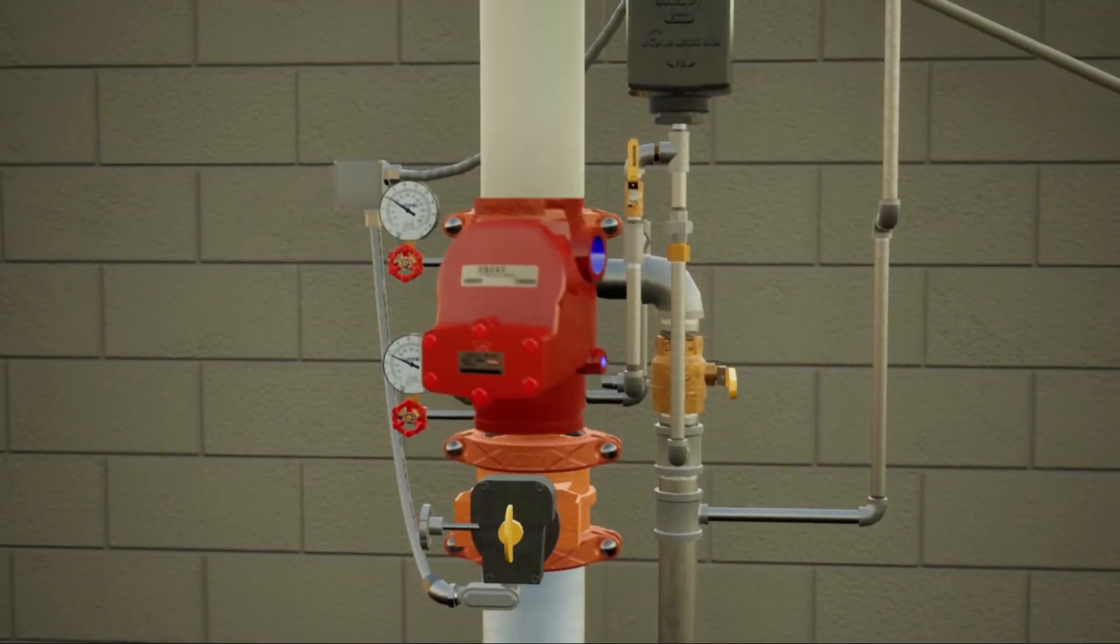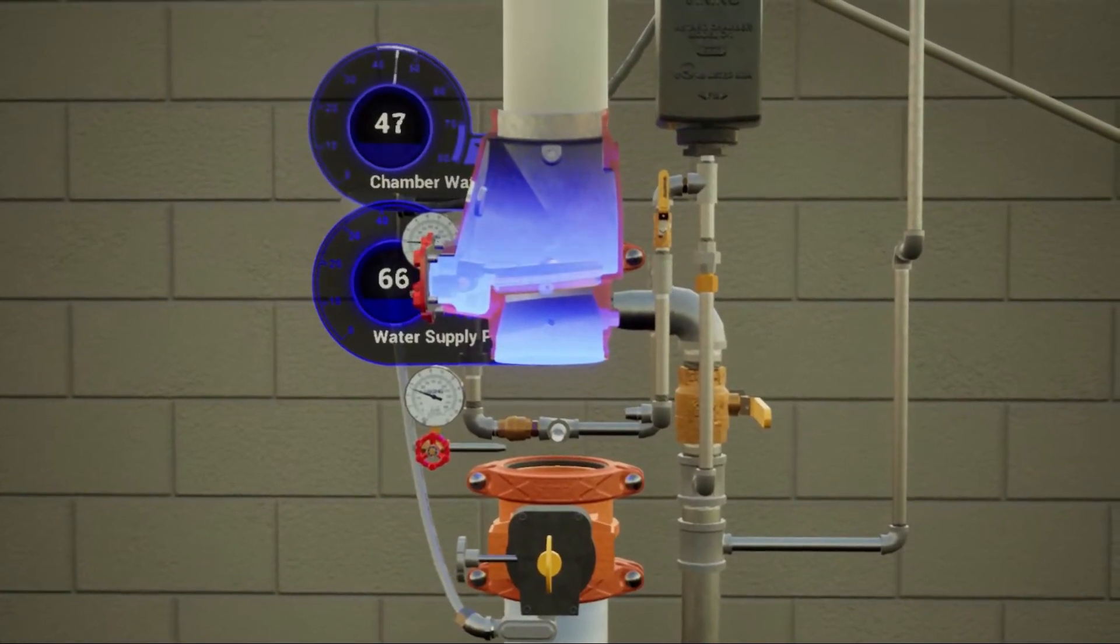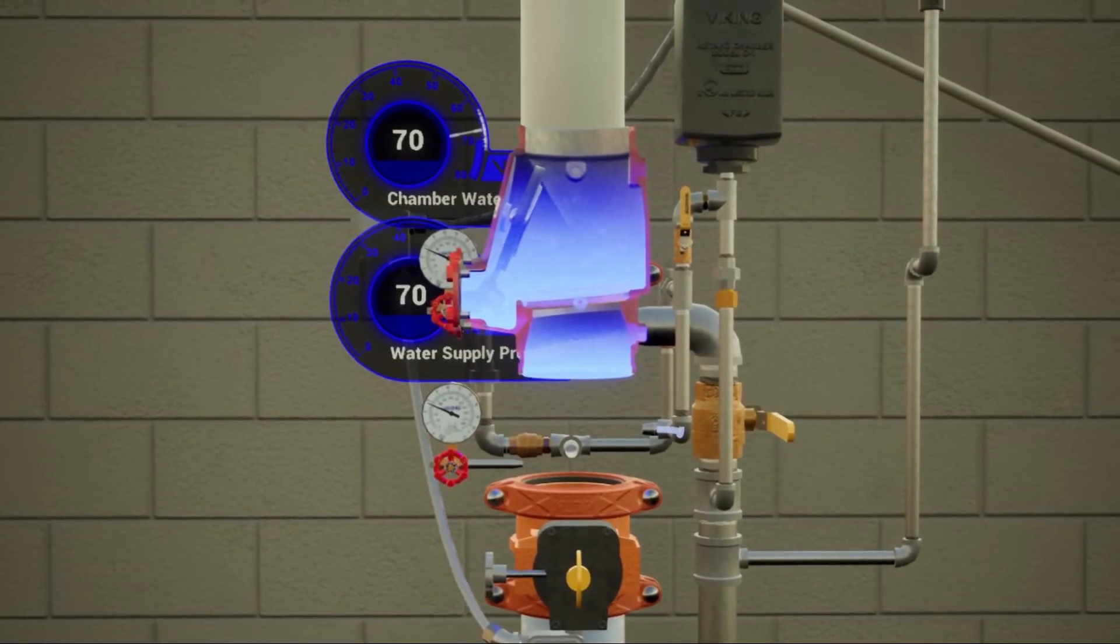After the sprinkler activates and water flow is established, the clapper is fully lifted off of the seat and the alarm ports are exposed, allowing water to enter and fill the alarm line.